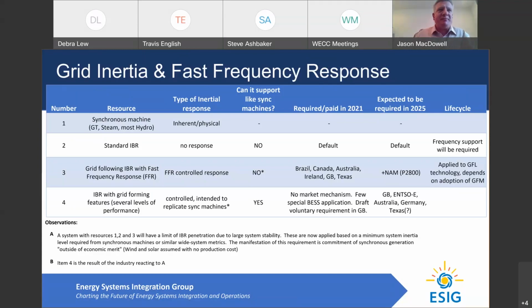But inverter-based resources don't have that direct coupling of inertia from the drivetrain onto the grid. So there's no inherent response; it needs a controlled response put in place that can inject energy at the right time to arrest the initial decline. Fast frequency response is one such controlled response that injects an initial amount of energy into the grid to help arrest that decline. It functionally mimics the energy given by synchronous machines, but it doesn't couple that energy directly onto the grid the way a synchronous machine automatically would.